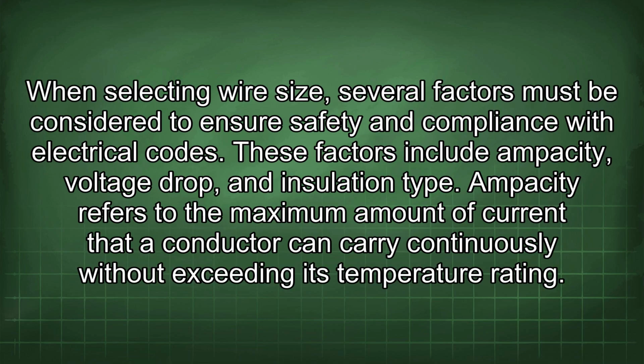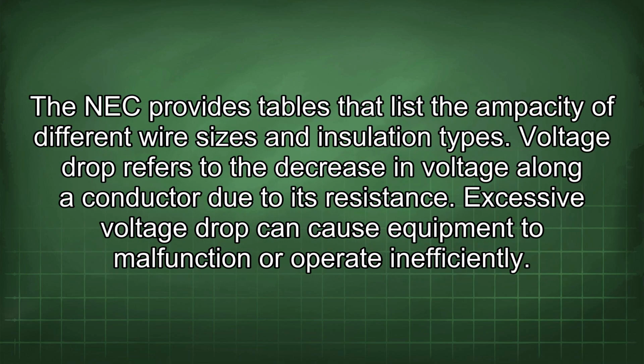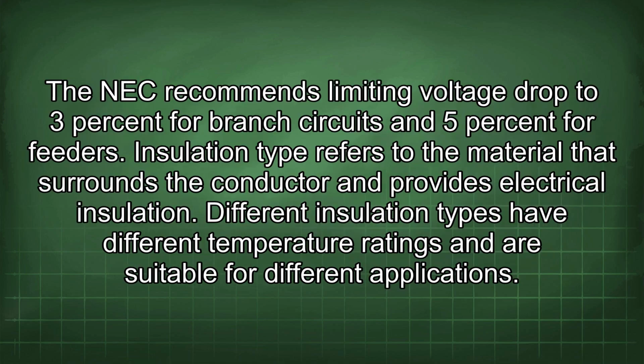When selecting wire size, several factors must be considered to ensure safety and compliance with electrical codes. These factors include ampacity, voltage drop, and insulation type. Ampacity refers to the maximum amount of current that a conductor can carry continuously without exceeding its temperature rating. The NEC provides tables that list the ampacity of different wire sizes and insulation types. Voltage drop refers to the decrease in voltage along a conductor due to its resistance. Excessive voltage drop can cause equipment to malfunction or operate inefficiently. The NEC recommends limiting voltage drop to 3% for branch circuits and 5% for feeders.